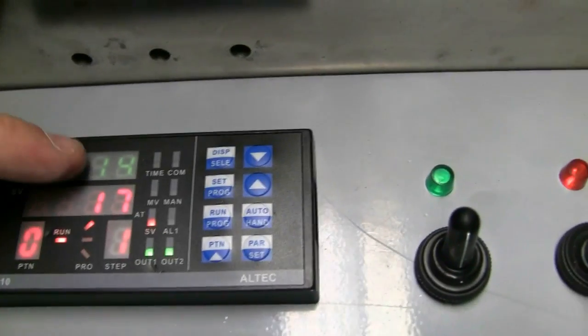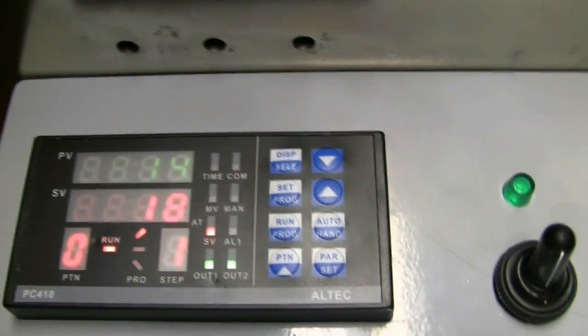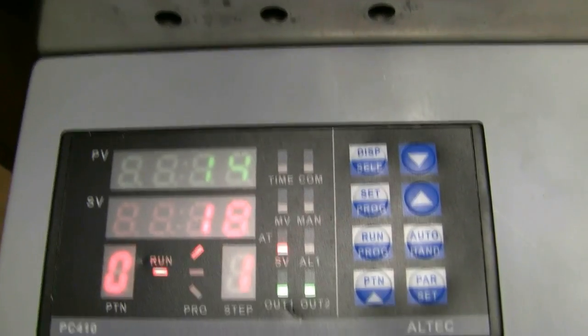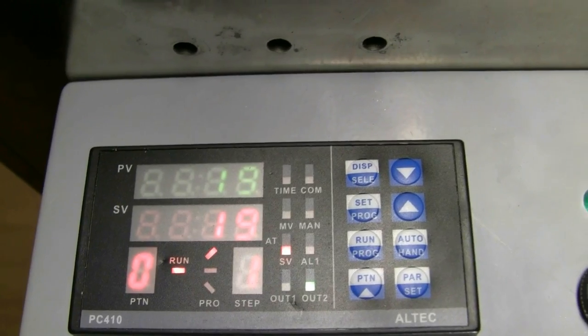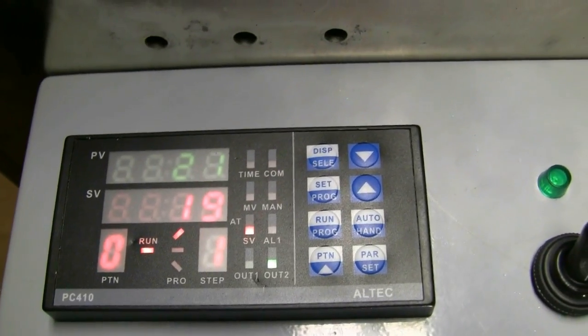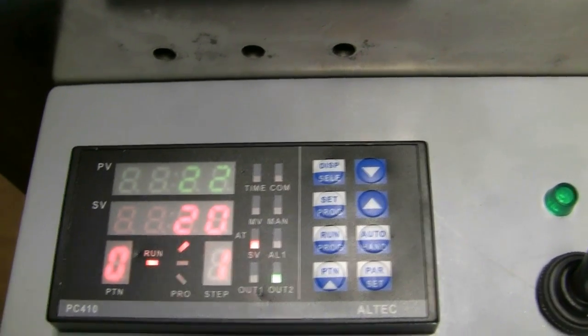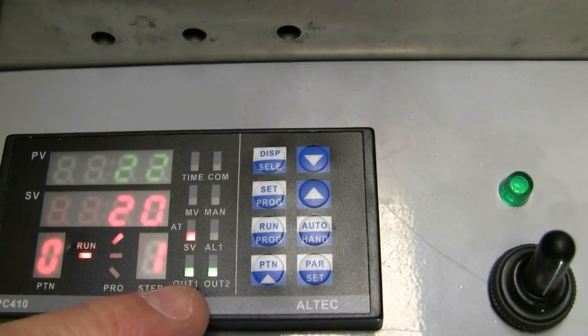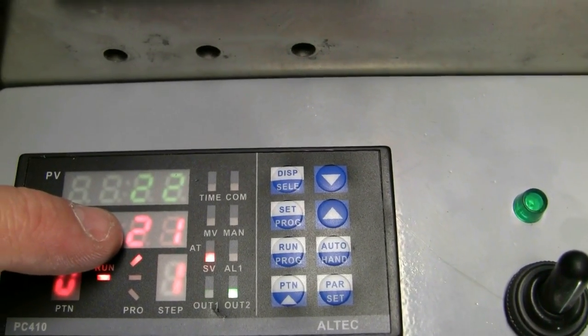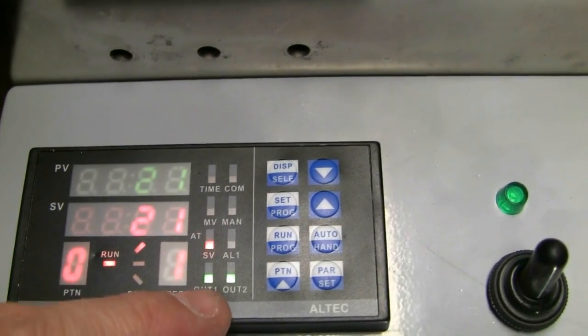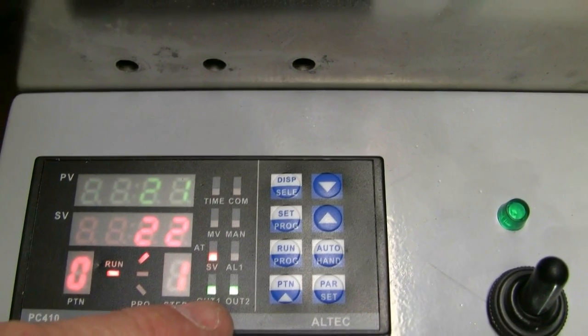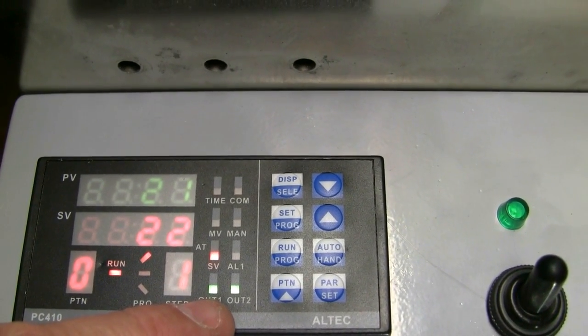It all works fine. If you look at what the PID controller is doing, it's reading a temperature at the moment of 14 degrees. This is the actual temperature on the thermocouple. So if I grab hold of the thermocouple, 16, 17, 18, 19. Because now the temperature of the thermocouple is higher than the set point, the output is switched off. As the set point approaches the thermocouple output, the output sort of flashes, and then finally once it gets a couple of degrees higher, it's on permanently.